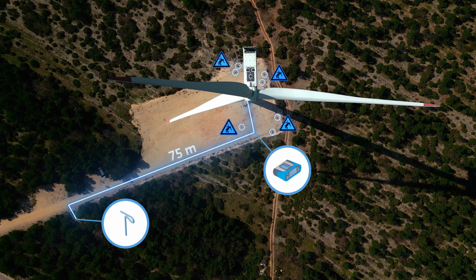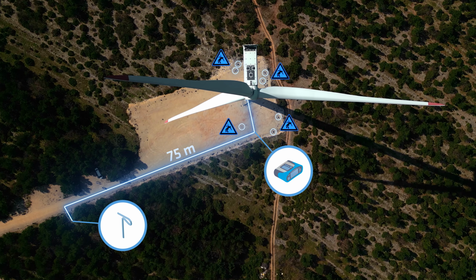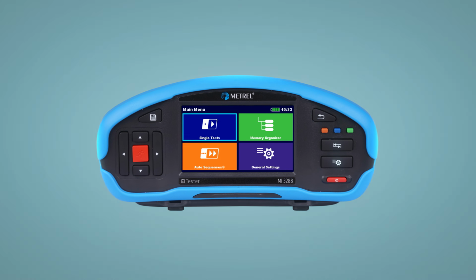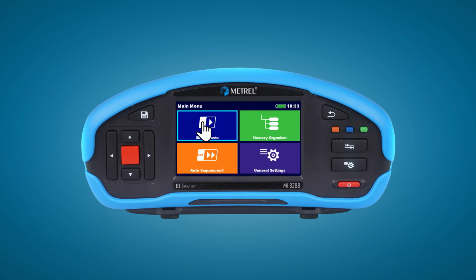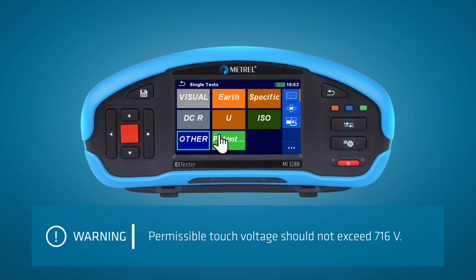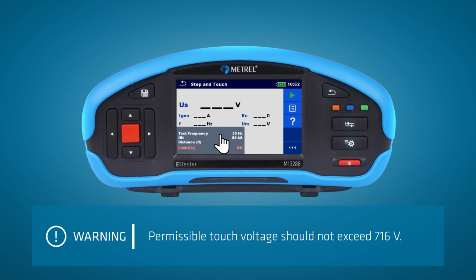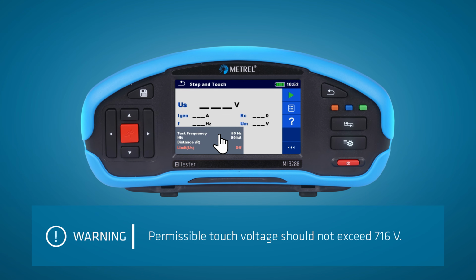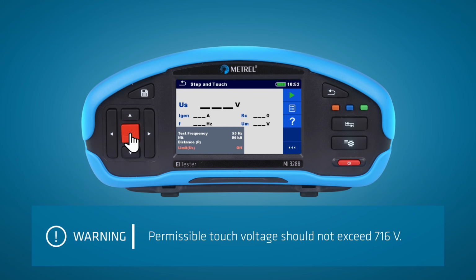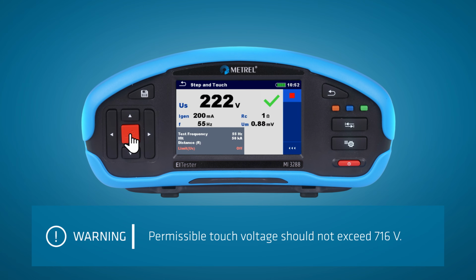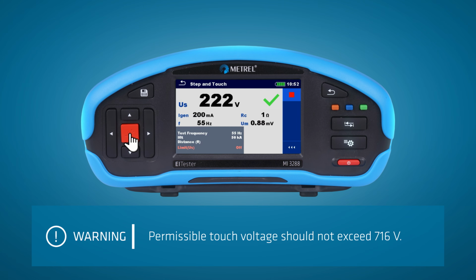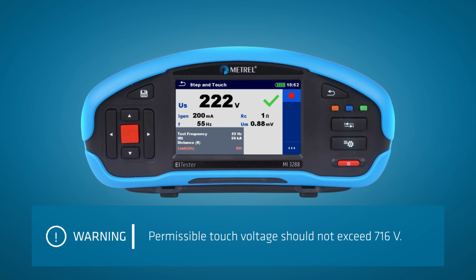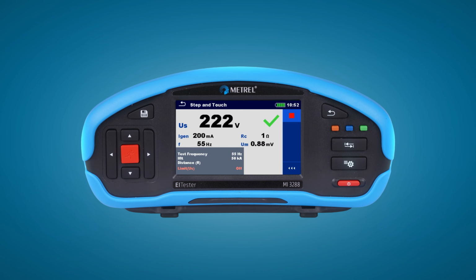Once all potential hazards have been identified and assessed, simply take your MI3288 tester, select single tests, and then choose potential. This opens the step and touch voltage measurement screen. Start the measurement. The result shows a voltage of below 716 volts at a current of 50 kiloamps, confirming that the installation remains safe in the event of a lightning strike.